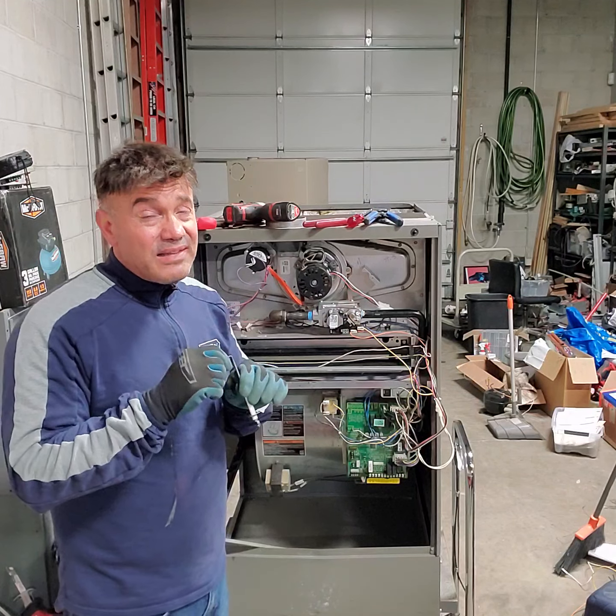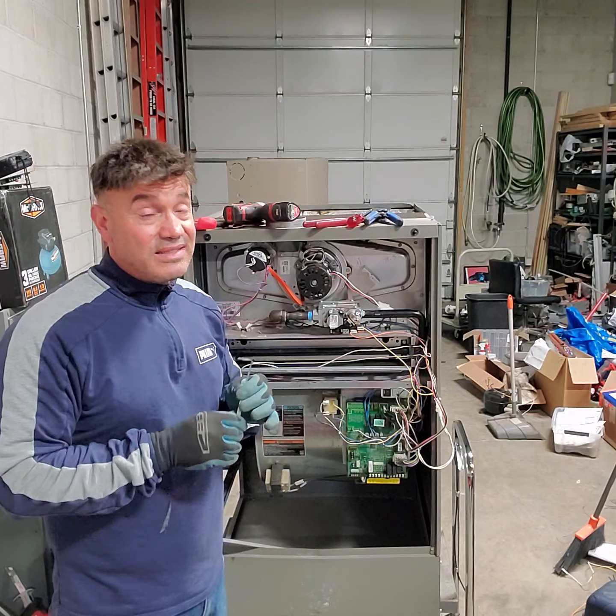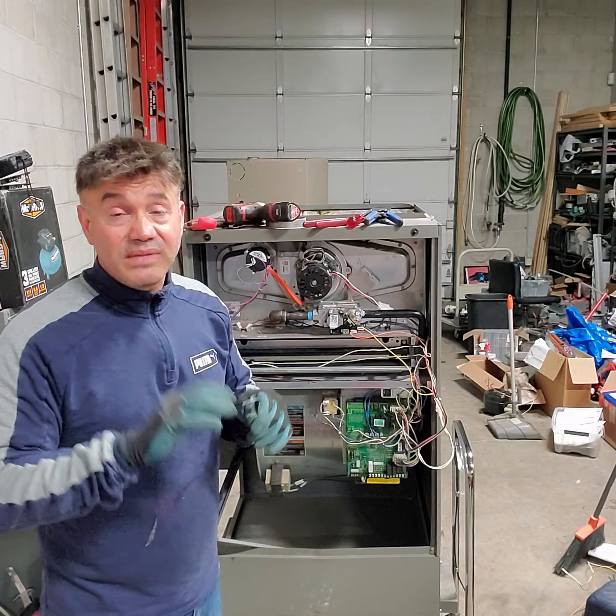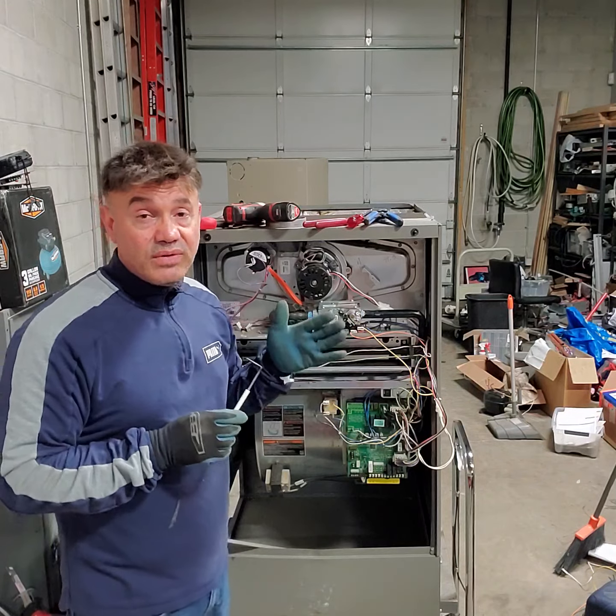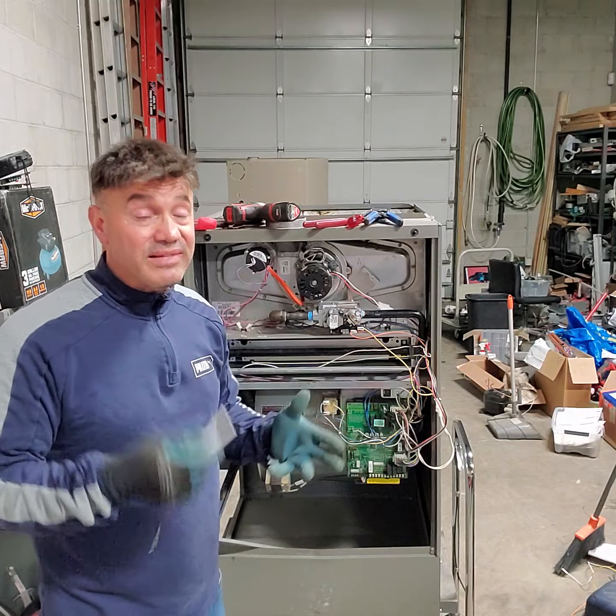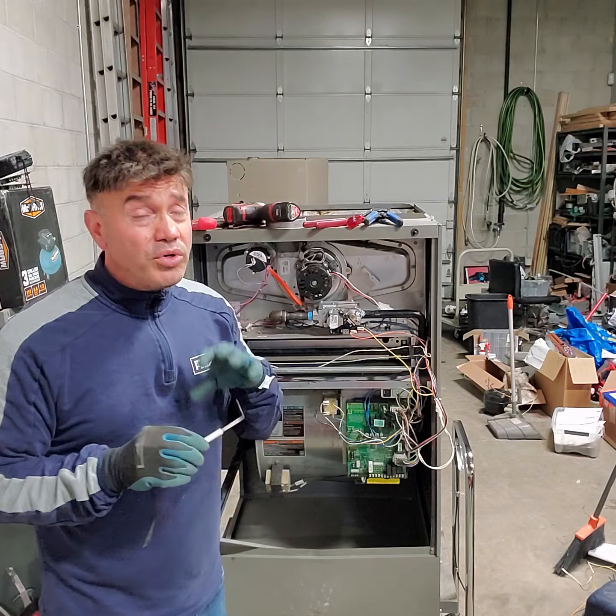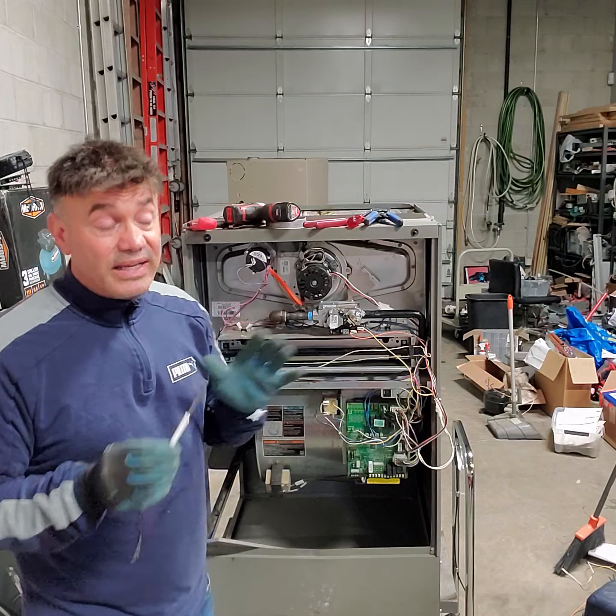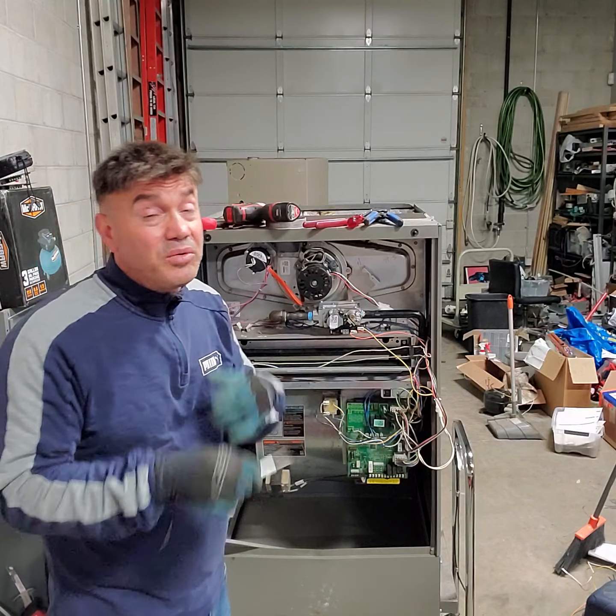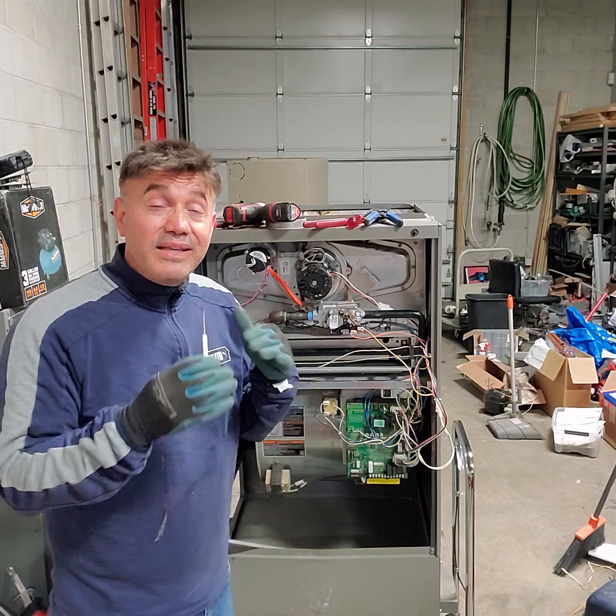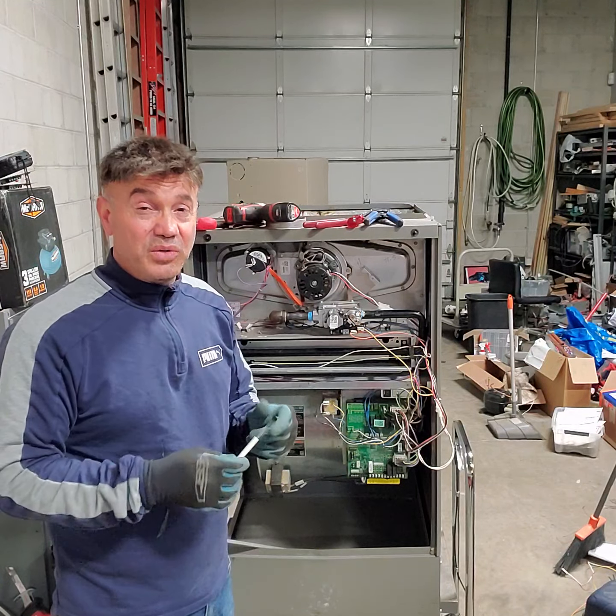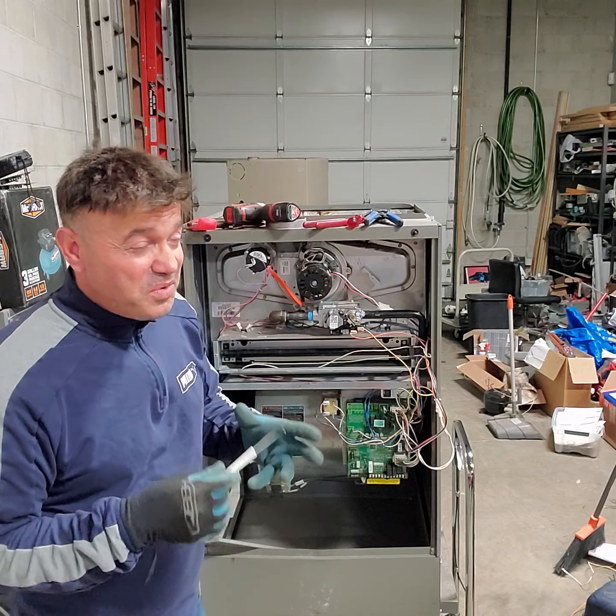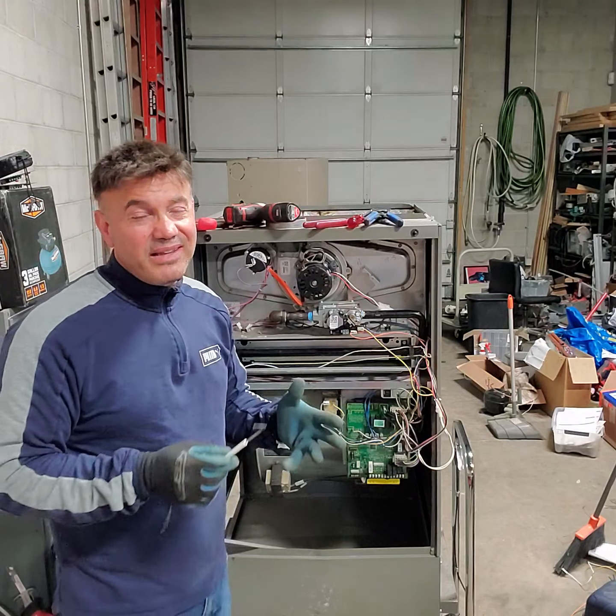Again, cleaning the flame sensor, in my opinion, isn't very reliable. Sometimes you clean it and it works for 6 months, maybe a year, and then you have the same problem again. The more you clean it, the less sensitive it becomes. Some people clean it and don't care as long as it's working, but the idea is you don't want to be gambling — when you clean it, you are gambling.